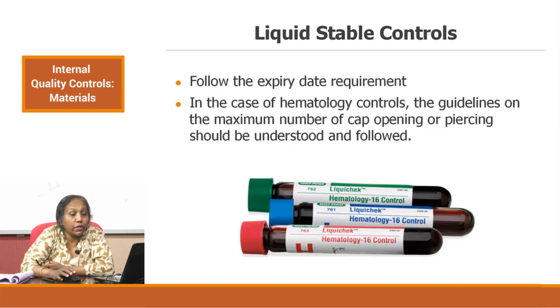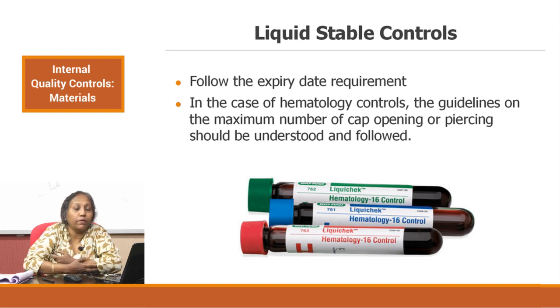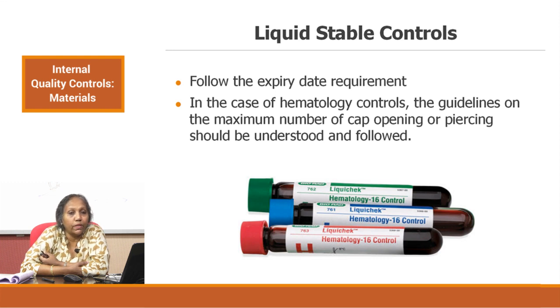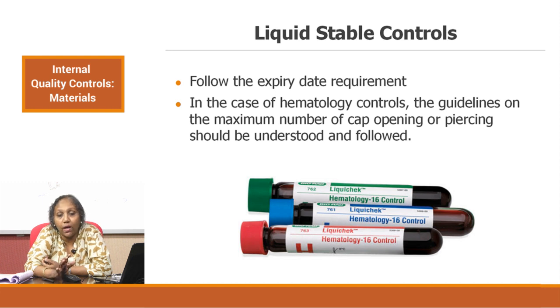When using liquid stable controls, you do not have to worry about all those reconstitution requirements — you just follow the expiry date requirement shown on the label. For hematology controls, cap-piercing and cap-opening mechanisms are available in most automated hematology analyzers. You should understand the number of times the manufacturer allows you to open the cap, how many cap piercings are allowed, and how many times opening and closing is allowed. Otherwise, you will find an undesirable and unacceptable amount of imprecision — not because of the analytical system, but because you have not preserved your material properly.